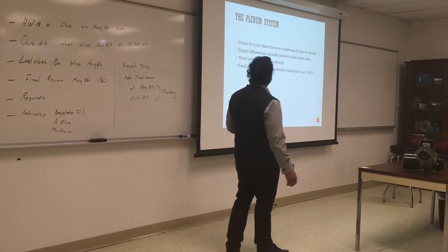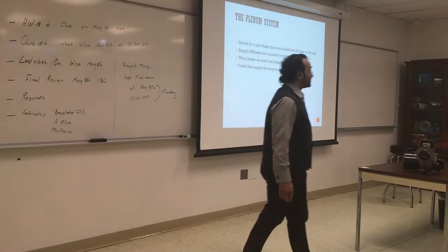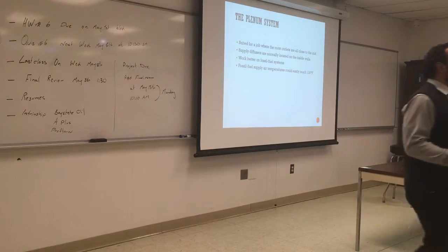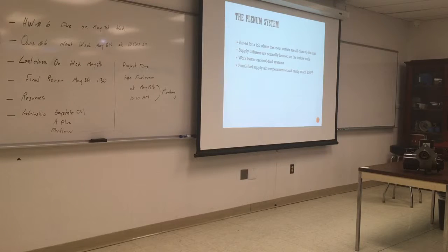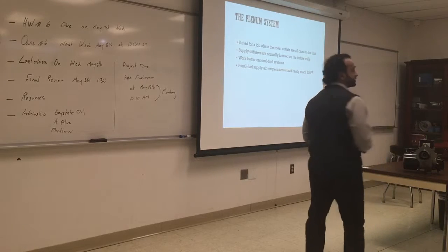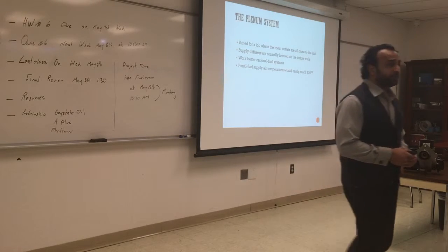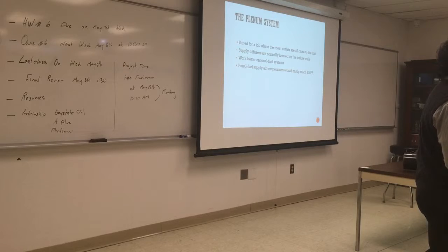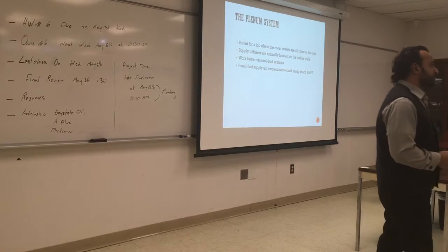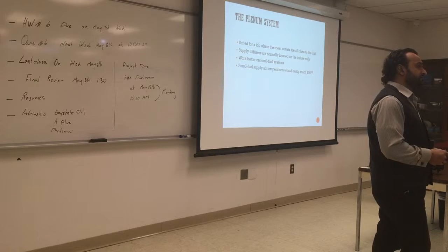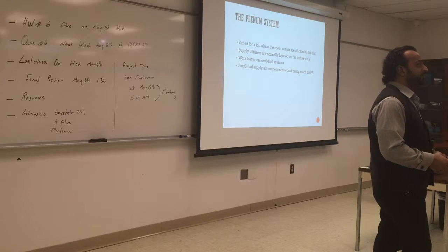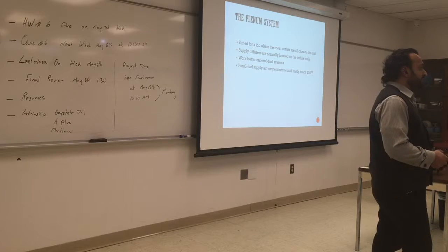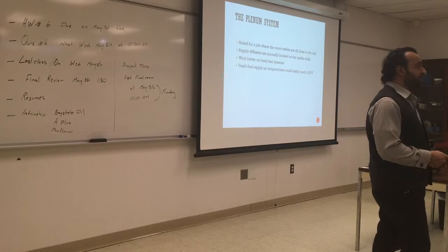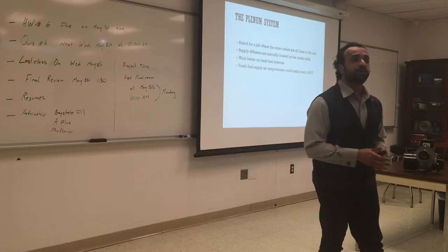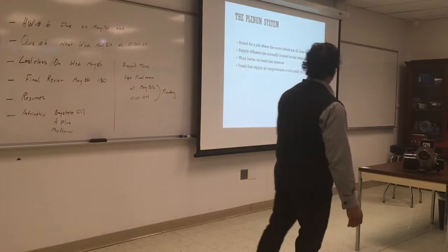Usually supply diffusers are located inside the walls. It works better with fossil fuel because you're required to have a lot of temperature. Fossil fuel is one of the only ways that you can supply temperature up to 130 degrees Fahrenheit. Heat pumps will not give you this much heat. Probably you'll be around 90 or 100. How hot do you want the air coming out of the register? If you want the room to be at 75, you want to be at least at 90, 95, 85. You don't want it to be very hot because that will affect the furniture or your comfort when a lot of hot air is pumping into the room.